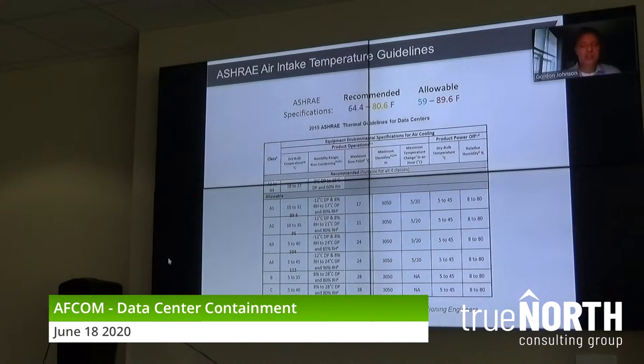What we're saying is, fix your problem, get your CRAC serviced, get it back and running, run it that way for a day or two or whatever's necessary, and get those temperatures back below 80.6. So again, that's the difference. Recommended, we want to be in that window. Allowable, we can go above recommended into that window, but we don't want to go above the allowable range of 89.6 for A1, 95 degrees for A2, or perhaps 104 for the A3 type server.